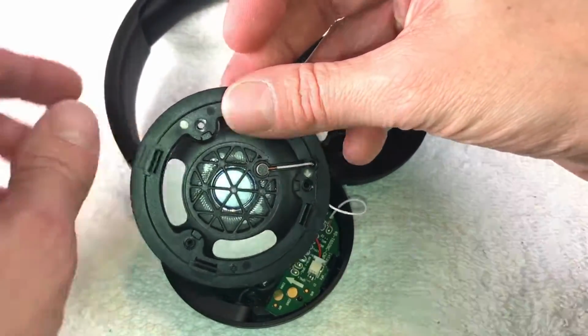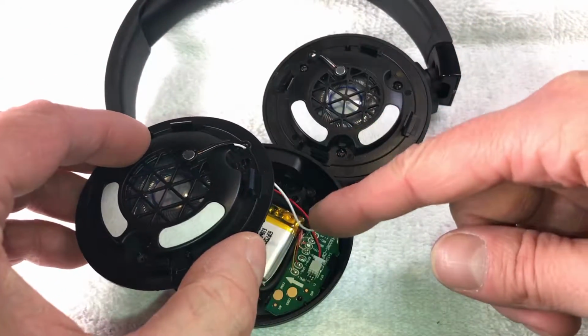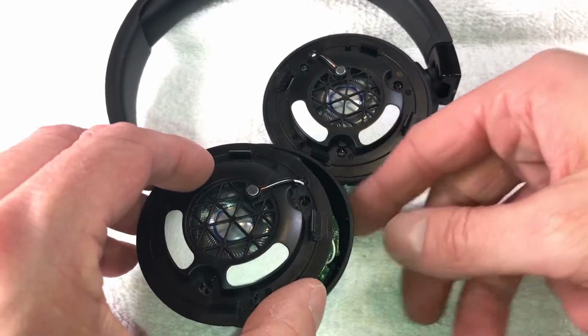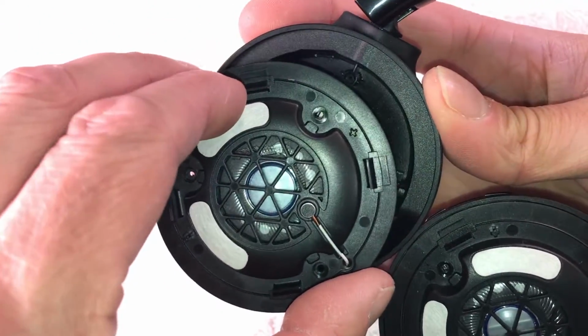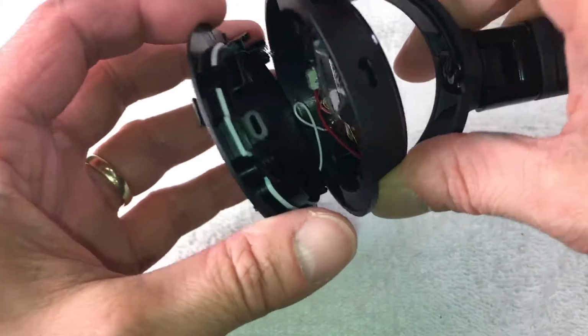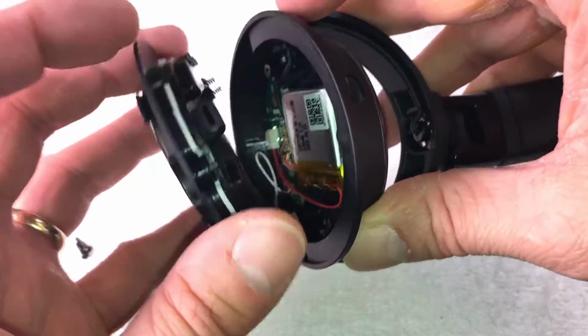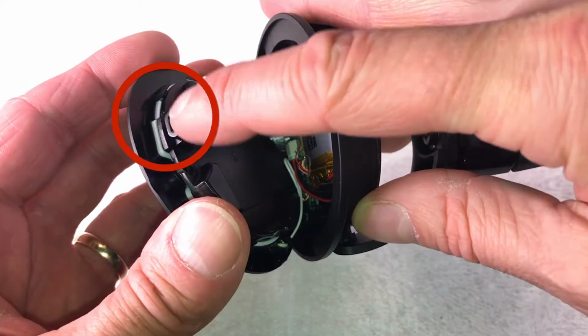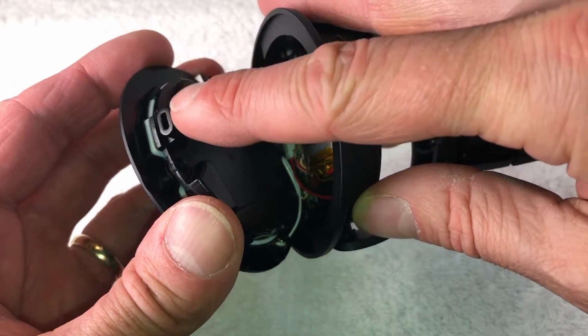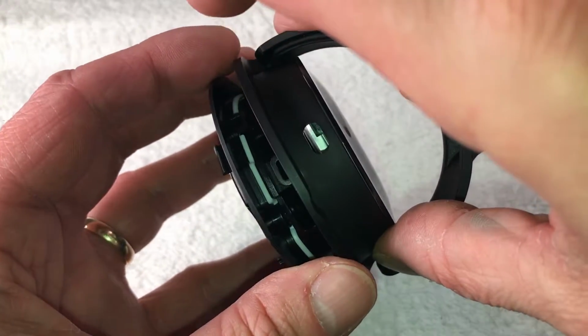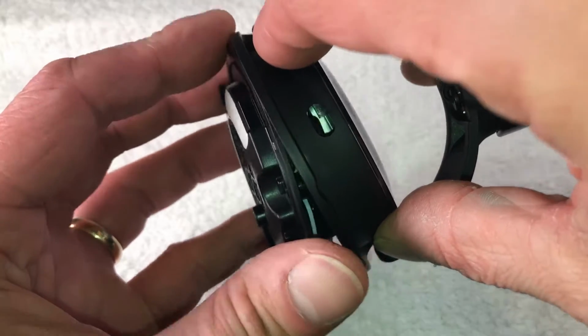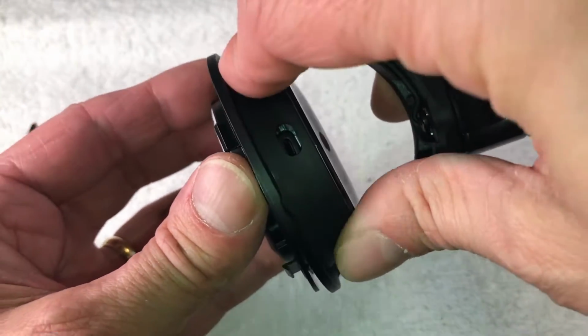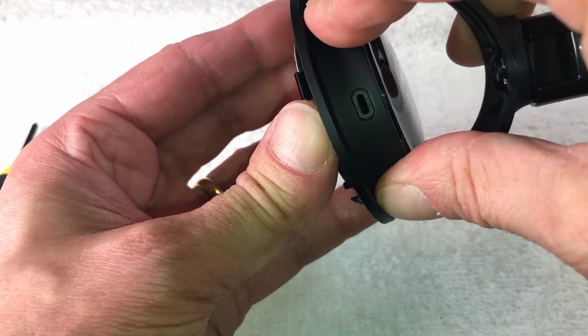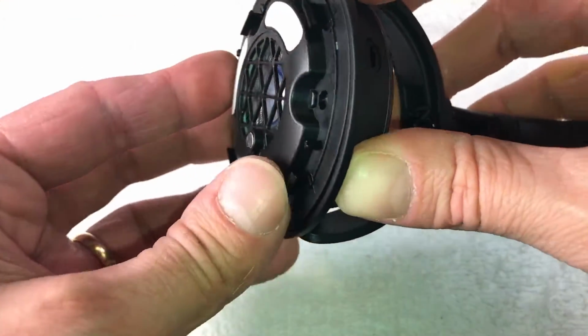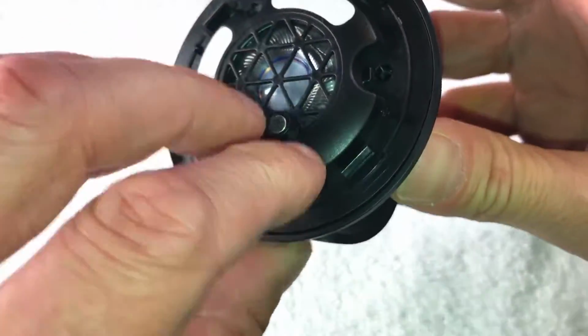Now that we have the battery installed, we can put this transducer back on. Make sure that the white wire isn't pinched. Also, in order to get the cover back on, you have to make sure that this port, which you see here in the red circle, goes in first on the outside of the housing. You see this little hole here, make sure the port goes through this hole first, and then we can simply push the transducer into position.